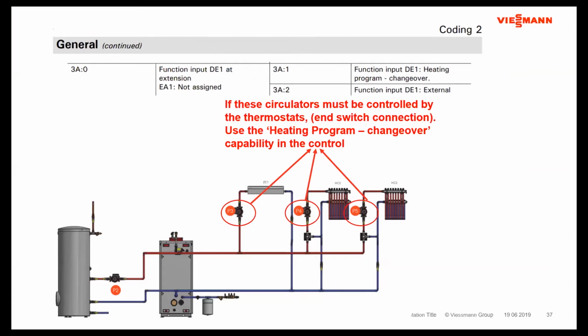Now, what if you wanted to turn these pumps off? It's always been one of these things with heating circuits. These pumps run 24/7. It's all about that keep up versus catching up. If you've taken some of our previous seminars, whether in class here or some of the online material that we've been providing, you always have the ability of starting and stopping these pumps. With heating circuits, it's about whether these pumps are required to start and stop. Do they have to stop because all the zones are closed? If they're a variety of pump that needs to stop, so not a variable speed pump that slows down based on pressure differentials, which doesn't really have to stop when the zones are closed. But if you have fixed 3-speed pumps, or you've put pumps on some sort of fixed flow or fixed pressure differential, then you may have to start and stop those pumps when these zones aren't calling anymore.